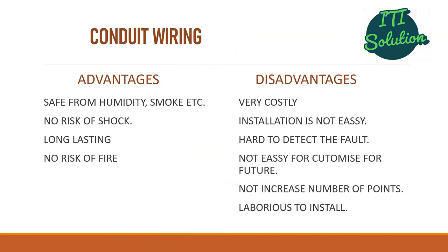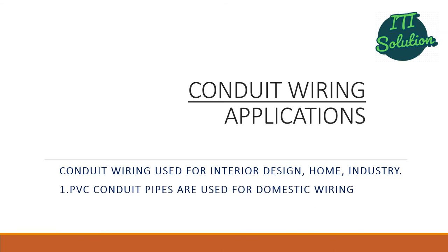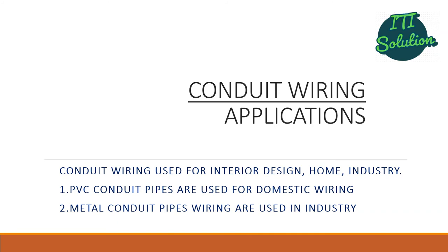Advantages of conduit wiring are safe from humidity, smoke, etc., no risk of shock, long lasting, and no risk of fire. Disadvantages are that it is very costly, installation is not easy, hard to detect faults, not easy to customize for future additions, and laborious to install. For applications, conduit wiring is used for indoor design, homes, and industry. PVC conduit pipes are used for domestic wiring and metal conduit pipes are used in industry.